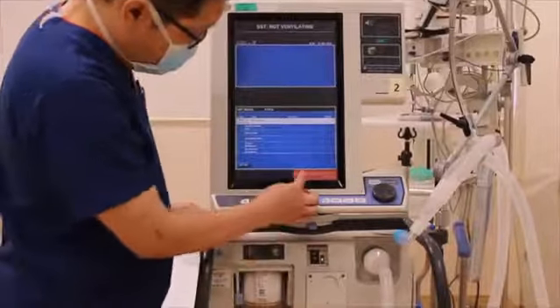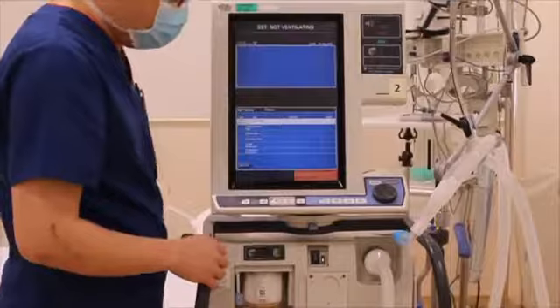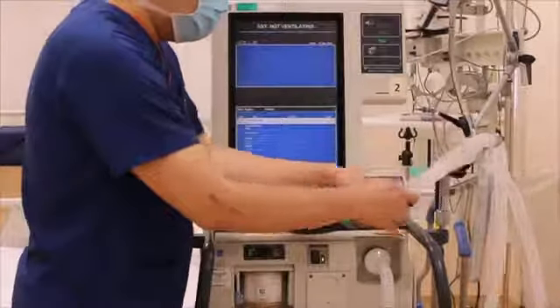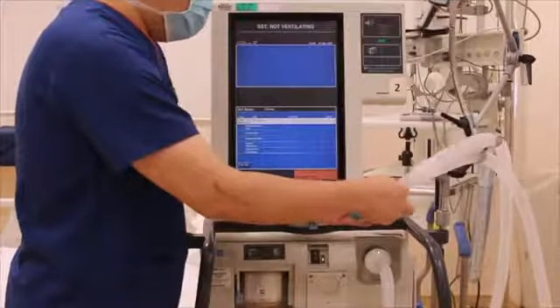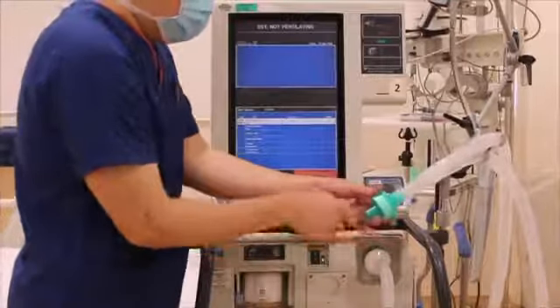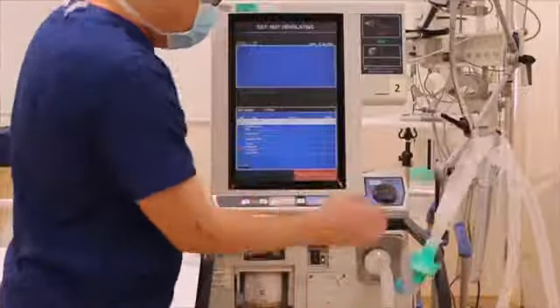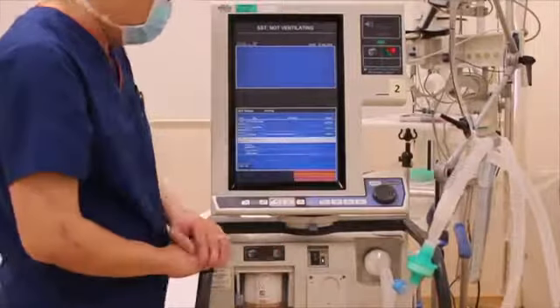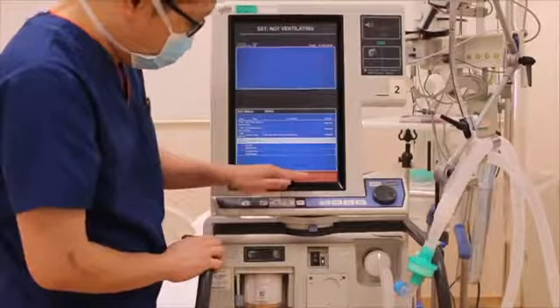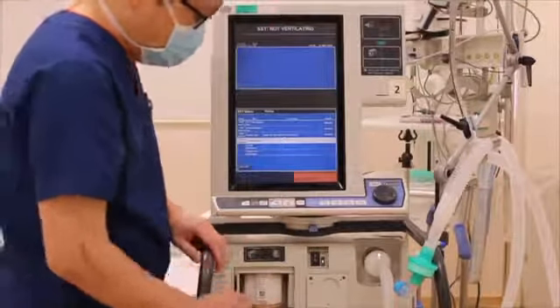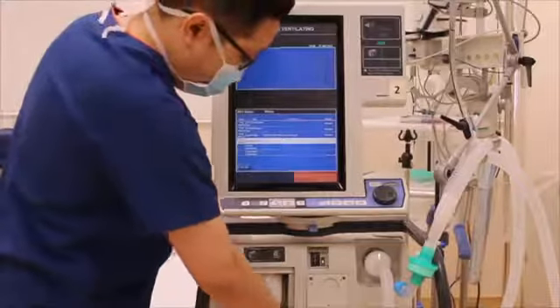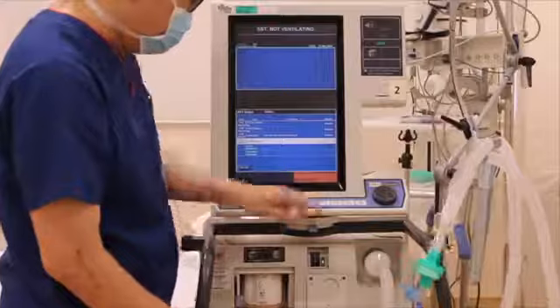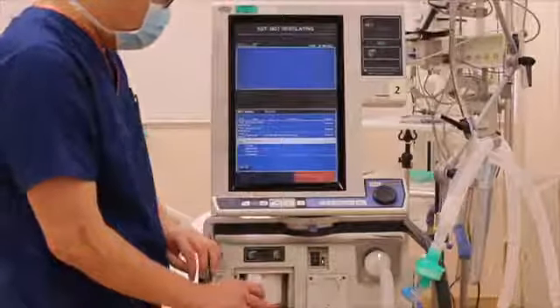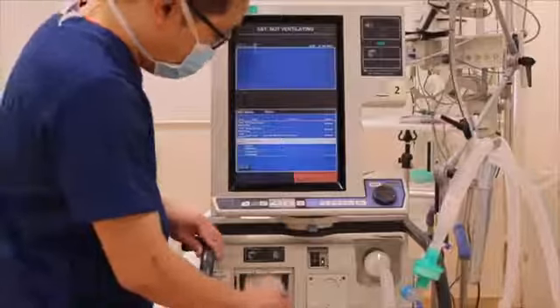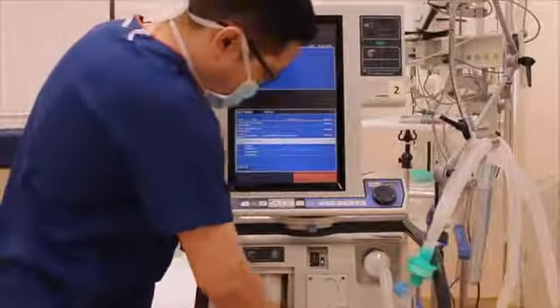The next step would be to connect the humidification if applicable. So for this demonstration, we are using an HME device. Connect the humidification filter into the system, and then press accept. The next instruction is to disconnect from the patient port. This is where you disconnect the expiratory limb from the expiratory valve. Once that is done, press accept again. When that is completed, it will ask you to connect the expiratory limb back to the expiratory valve. Make sure that it's snugly tightened. Press accept.